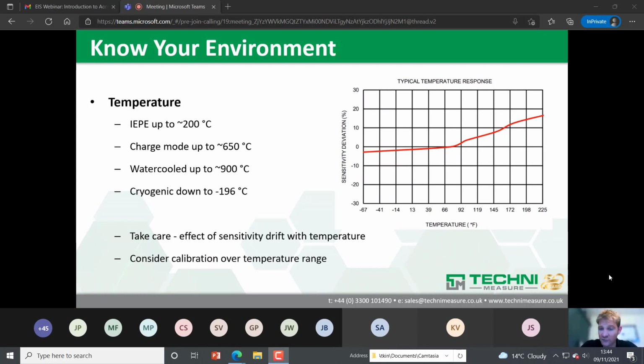Here's a typical example of a general purpose accelerometer. You can see as we're getting up to the top end, we're seeing a sensitivity deviation of up to 15%, which would be undesirable. If it's important to you, if you've got a big change in temperature, then you might consider having the accelerometer calibrated over the temperature range, which is where a calibration house would use a climatic oven with a shaker to calibrate the frequency response of this accelerometer over a temperature range.